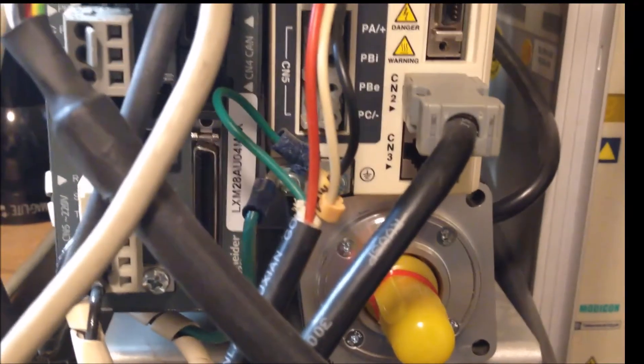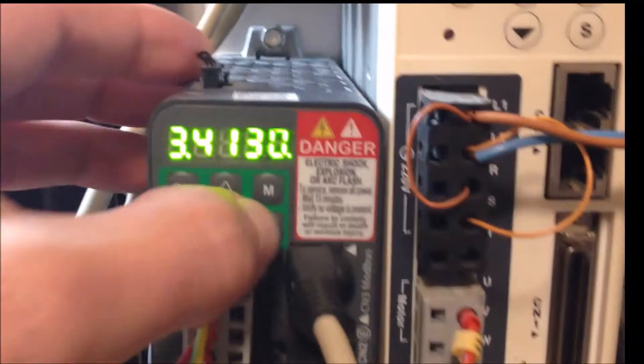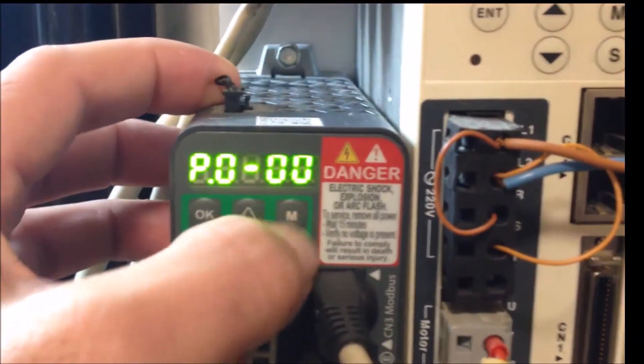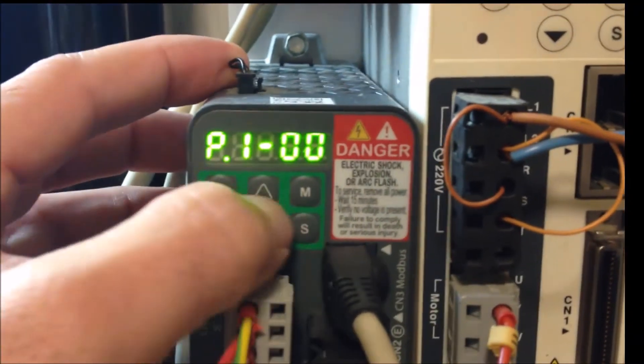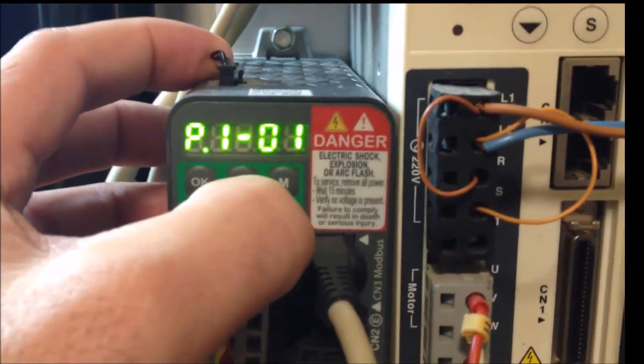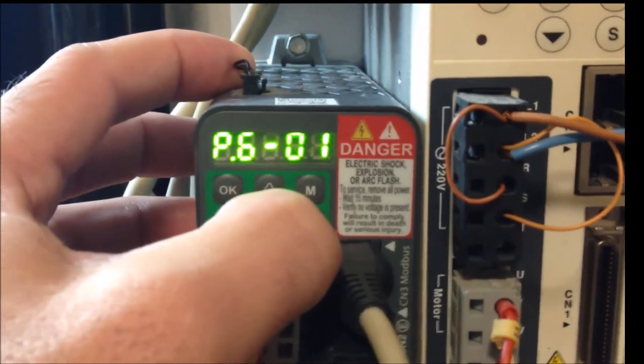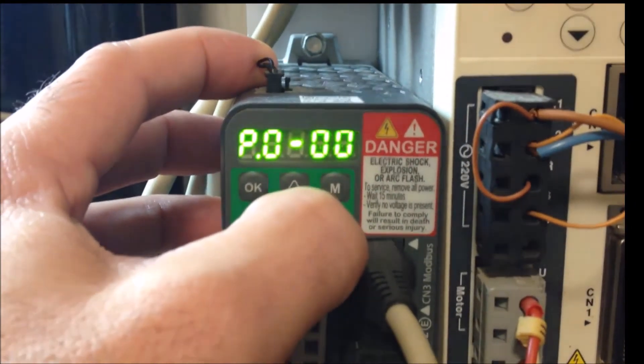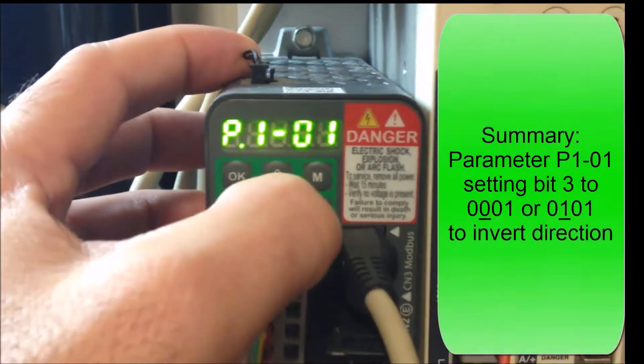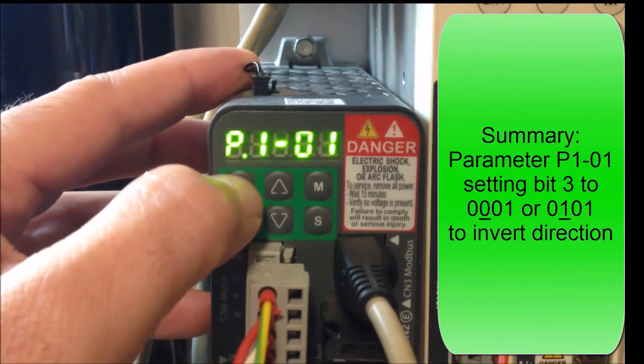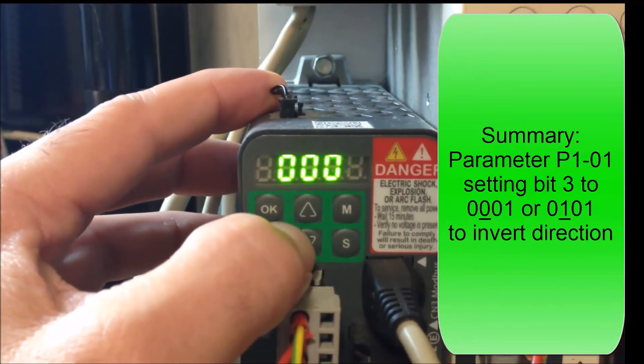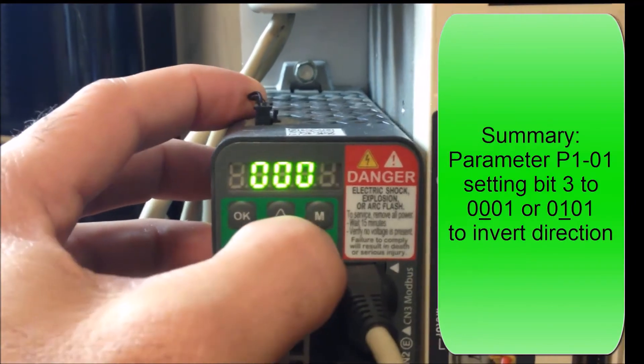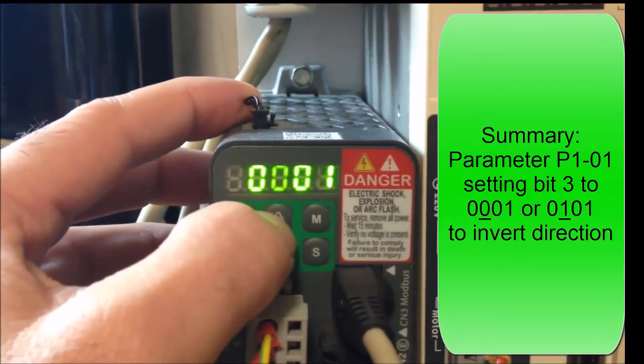That's all there is to it. Parameter p1-01, the third digit - changing the third digit inverts the direction of rotation.